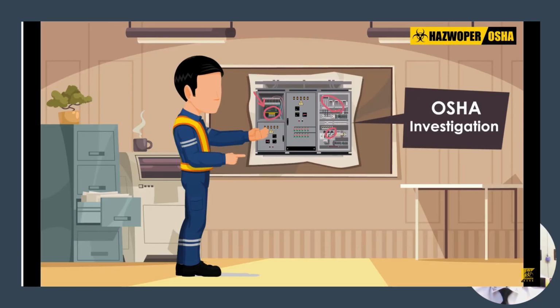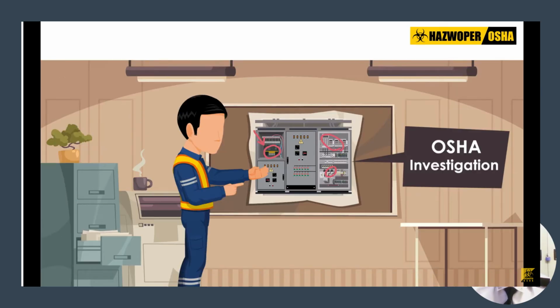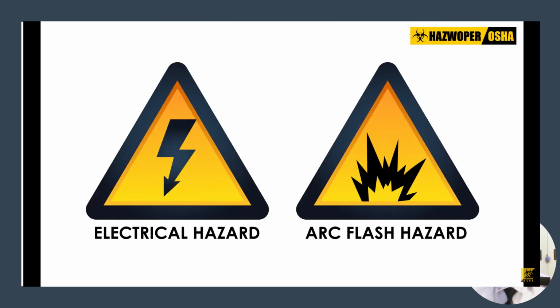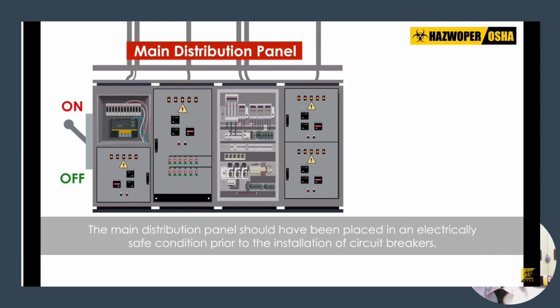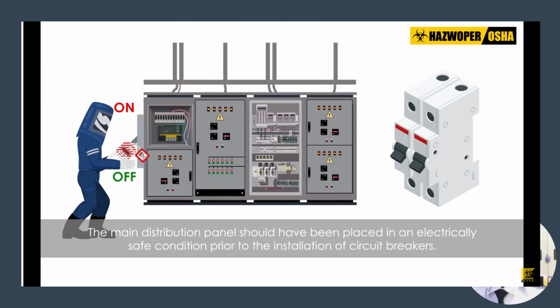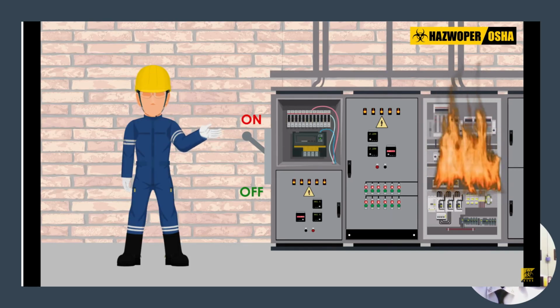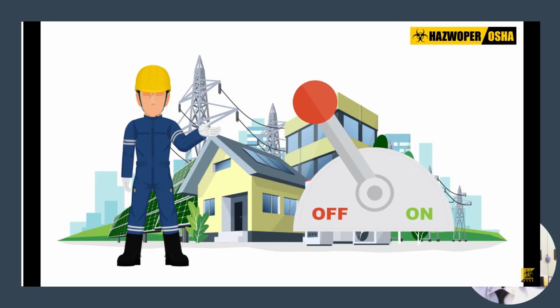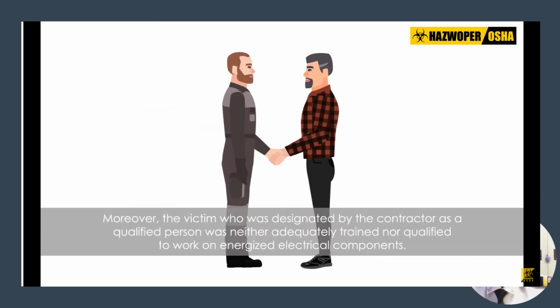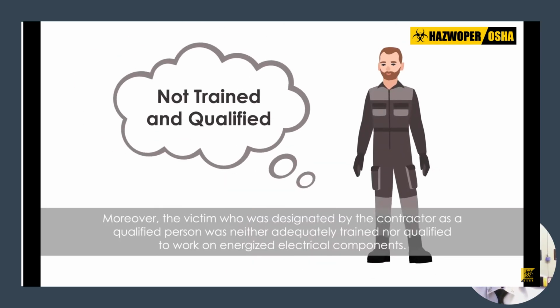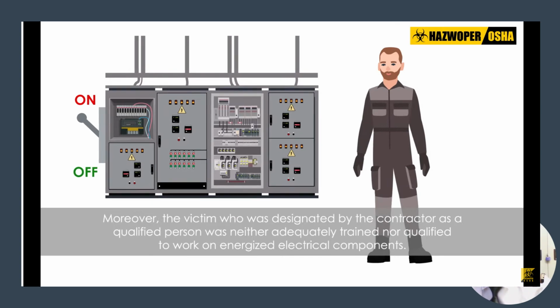OSHA investigation into the incident concluded that the arc flash and subsequent injury could have been prevented by adhering to basic electrical safety principles. First and most importantly, the main distribution panel should have been placed in an electrically safe condition prior to the installation of circuit breakers. The apparent justifications for failing to de-energize electrical equipment in this incident, which focused solely on the inconvenience of shutting power off, do not meet the necessary conditions for working on or near energized electrical components under the NFPA 70E. Moreover, the victim, who was designated by the contractor as a qualified person, was neither adequately trained nor qualified to work on energized electrical components.